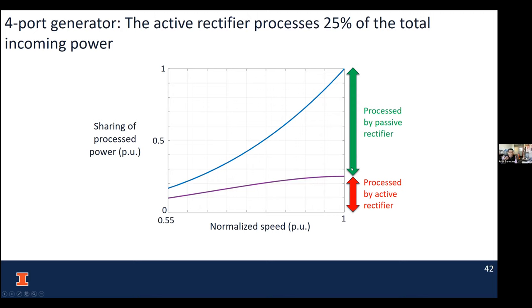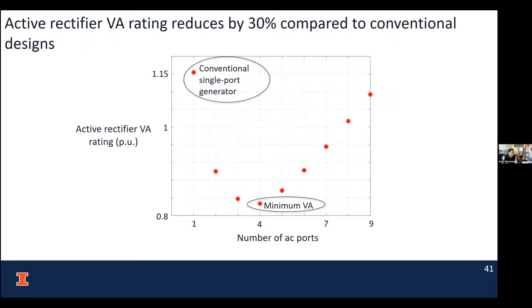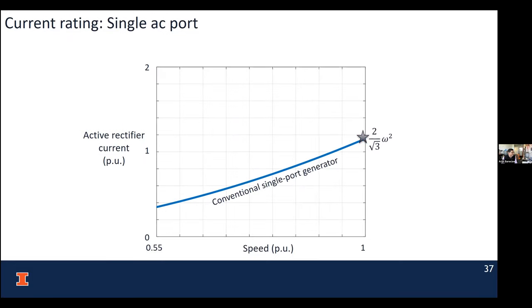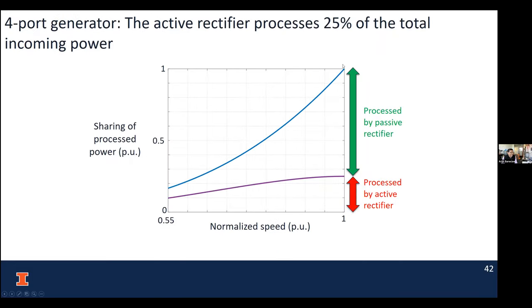That's kind of obvious if you think about it for a moment. In a four port system, when I'm at rated speed, three ports' worth of power comes from the passive rectifier -- that's 75% -- and 25% of the power goes through the active rectifier. Think about it in terms of a 10 megawatt wind turbine: if it's running at rated speed, only 2.5 megawatts has to be processed by the active rectifier, and that reduces the losses in the active rectifier.